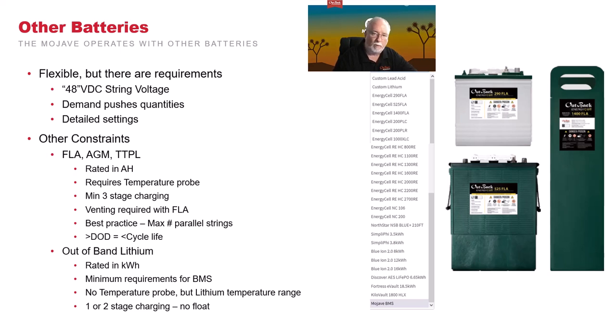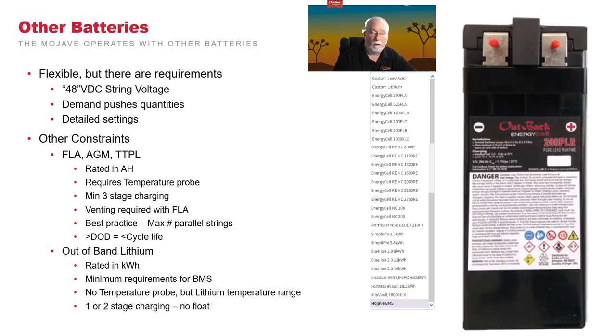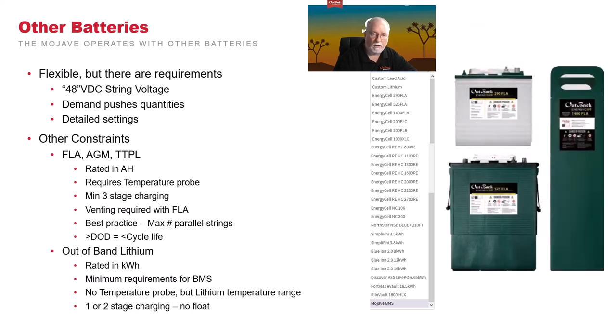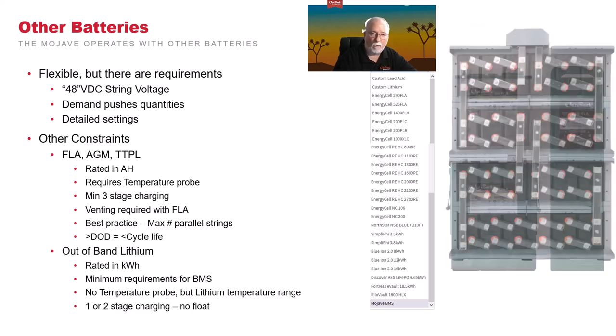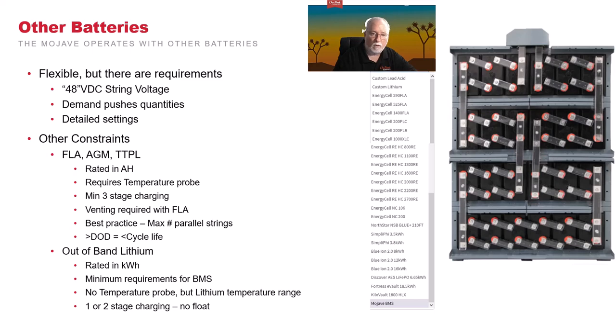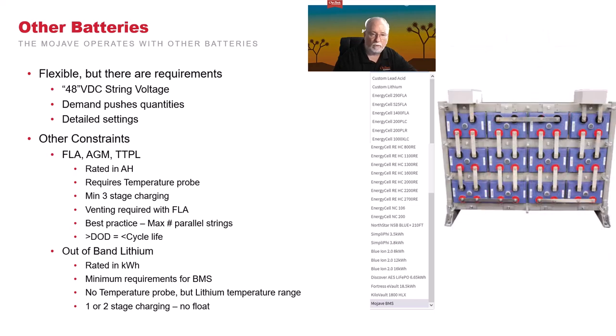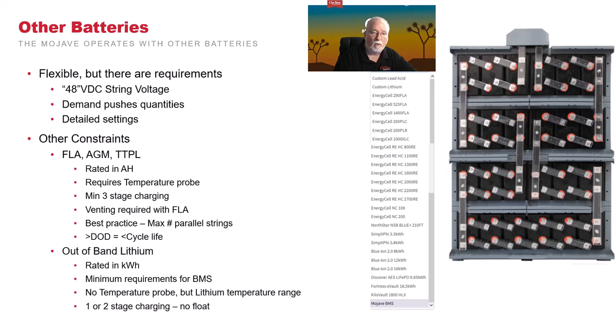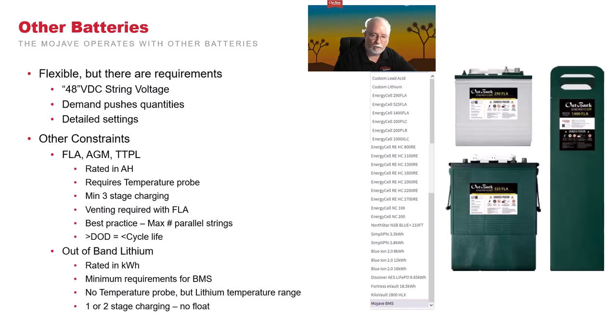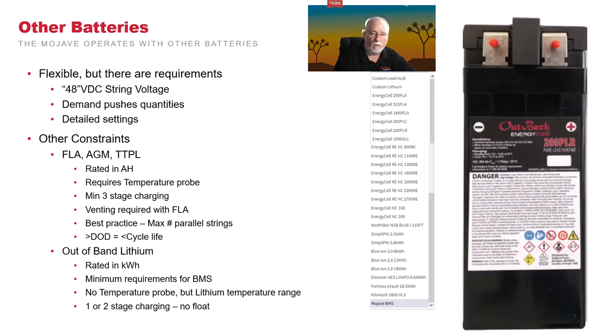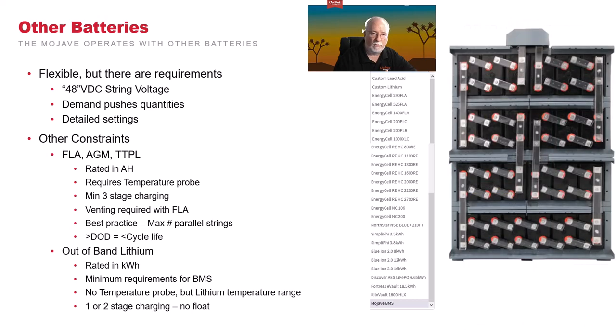Best practice for putting them in parallel, and make sure that you understand the depth of discharge. The further you take them down, the more you reduce the life cycle of the batteries. There's also out-of-band lithium. These are rated in kilowatts. There is a minimum requirement to not overload the BMSs in these batteries and trip them. There's no temperature probe, but lithium does have a temperature range. And those are normally supported through 1 or 2-stage charging. In other words, just a bulk, possibly a short absorb, but no float charging of the lithium batteries at all.